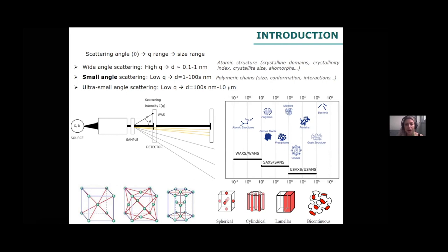Wide-angle techniques reveal structures ranging from 0.1 to 1 nanometer — in the case of carbohydrates, we can study crystalline structures. If we move the detector farther from the sample, we register lower angles and are working with small-angle scattering techniques. In that case, we can study size ranges from one to several hundreds of nanometers, which for carbohydrates means we can study the structure of polymeric chains — their size, conformation, and interactions.